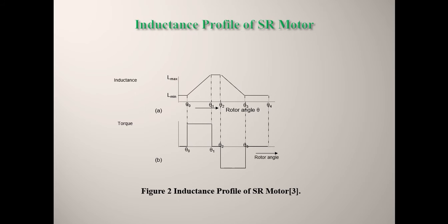The inductance profile for the SR motor is given in figure number two. We see that there is L_minimum and L_maximum. Inductance maximum occurs when both poles are exactly on the same axis — exactly opposite each other. Torque is positive when inductance is increasing and torque is negative when inductance is decreasing. This is the inductance profile of the motor.